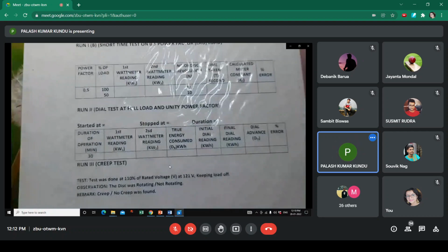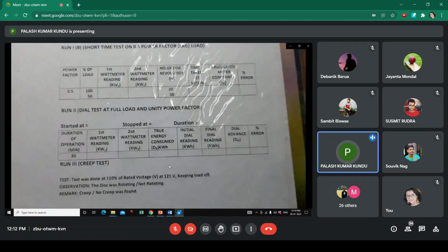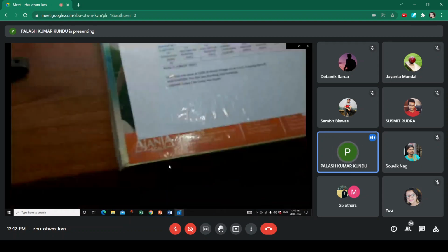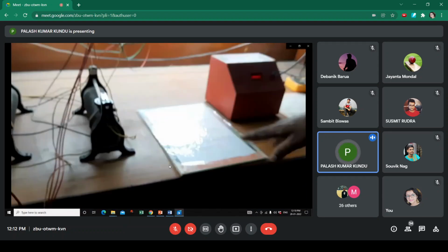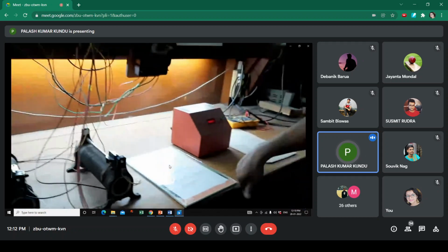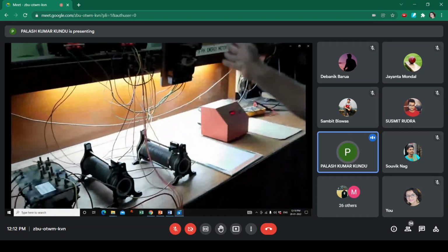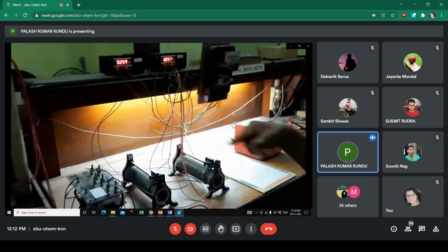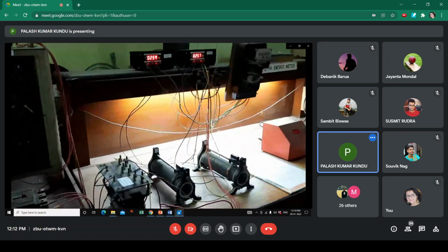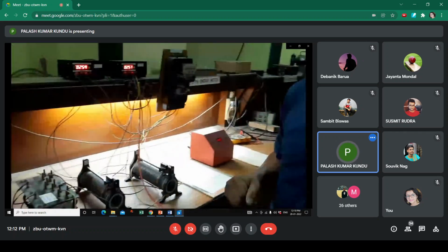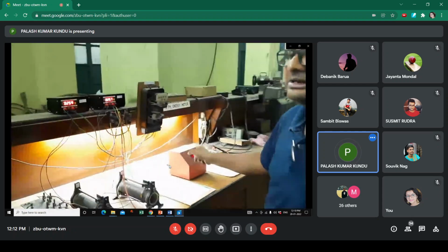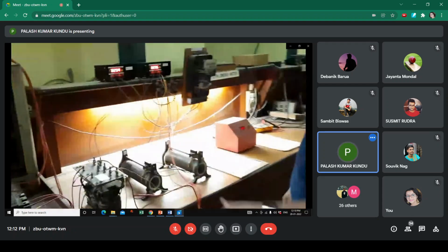Now, our last test is the creep test. For the creep test, we will switch off the supply of the current coil. So only the potential coil will be excited. There will be no supply to the current coil.